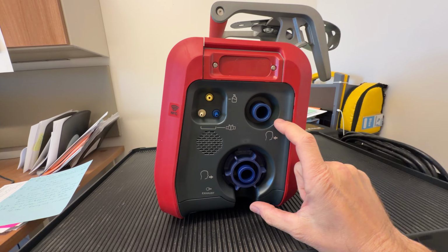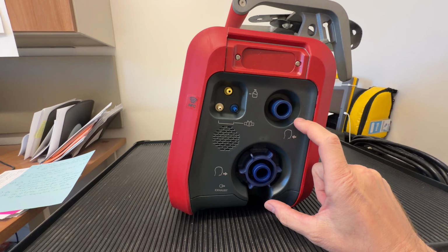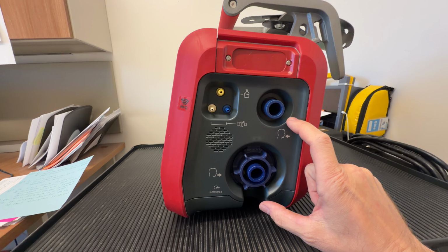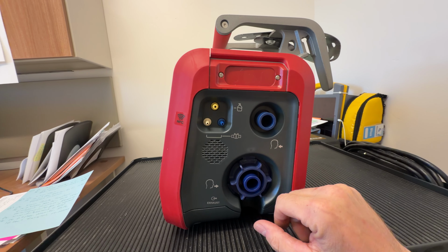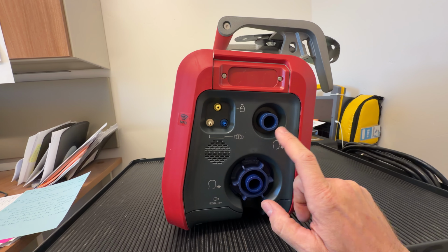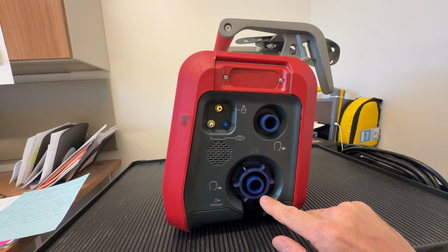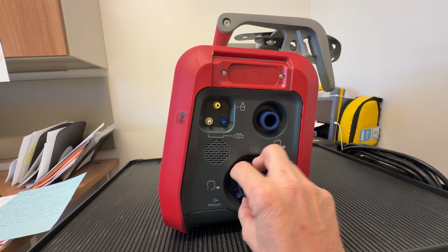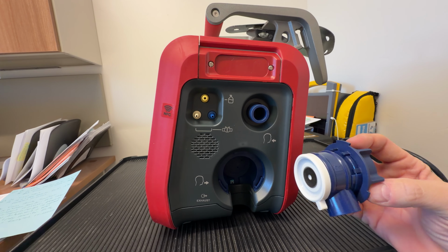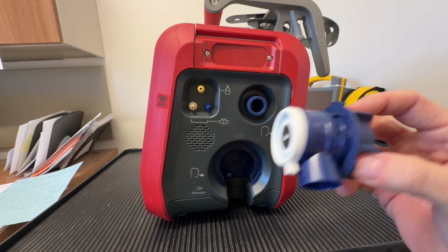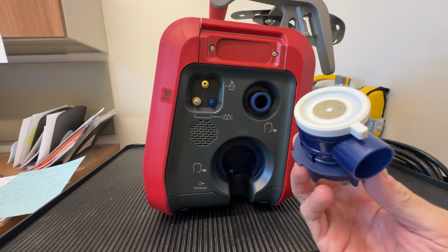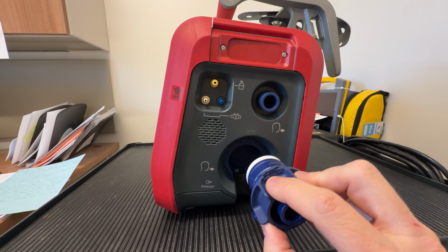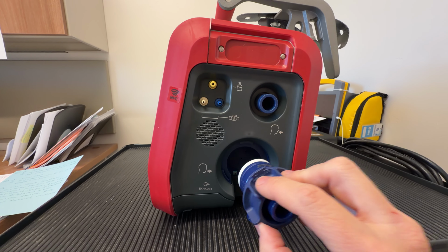to this side here. All right, so this is where your ventilator circuit will attach, and it doesn't matter if you're using the coaxial or the Y circuit. You're going to have your inspiratory limb connect up here, your expiratory limb connect up here, and you do need to have an expiratory valve. This blue expiratory valve actually comes with the ventilator, and you can see the opening there goes down.